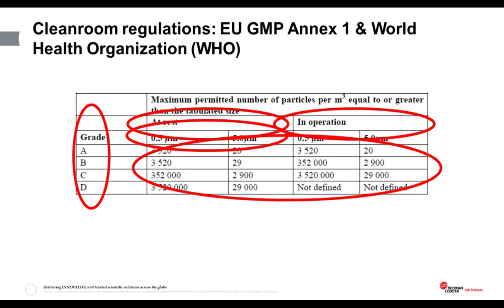Let's take a look at the GMP regulations controlling contamination levels in these clean rooms. This is the current table for air particle contamination in the European GMP Annex 1, which is also the same in the World Health Organization's guide for sterile manufacturing. There are four grades of clean room defined, from the very cleanest — grade A — through to the dirtiest — grade D. The European GMP calls for two particle sizes to be measured and reported: 0.5 micron and 5 micron particles.